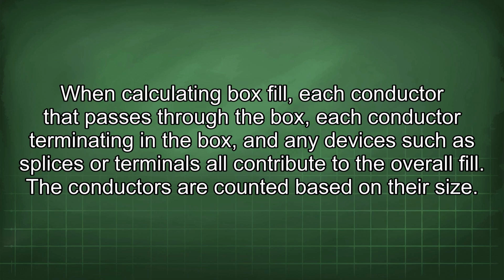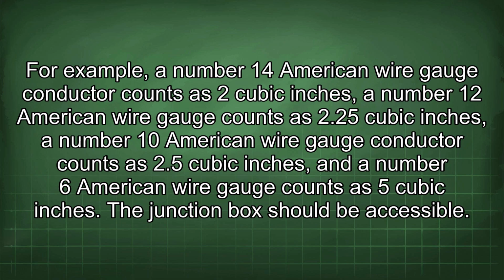When calculating box fill, each conductor that passes through the box, each conductor terminating in the box, and any devices such as splices or terminals all contribute to the overall fill. The conductors are counted based on their size. For example, a number 14 American wire gauge conductor counts as 2 cubic inches, a number 12 American wire gauge counts as 2.25 cubic inches, a number 10 American wire gauge conductor counts as 2.5 cubic inches, and a number 6 American wire gauge counts as 5 cubic inches.